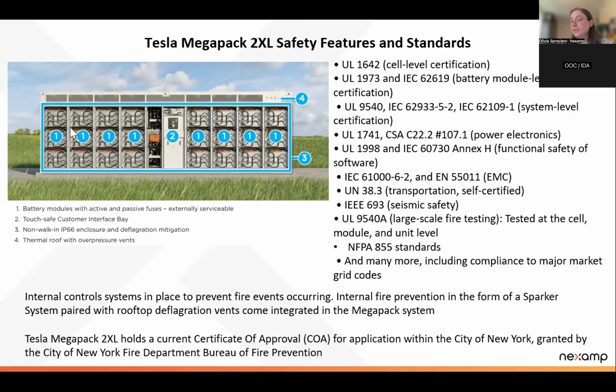Some of the safety features of the Tesla Megapack: it has built-in monitors for just about everything, temperature on a cell level, pressure, whether voltages are changing. All of that gets reported to our 24/7 response team, but it's also reported to Tesla at the same time, 24/7, every day, all day. We can see if we need to keep monitoring the temperature, the pressure, and the amount of energy going through the system.